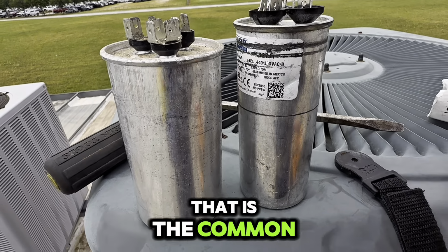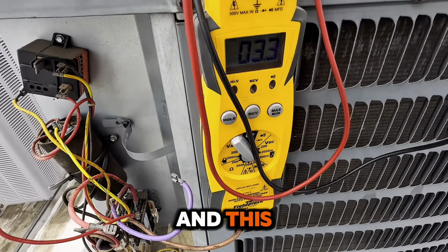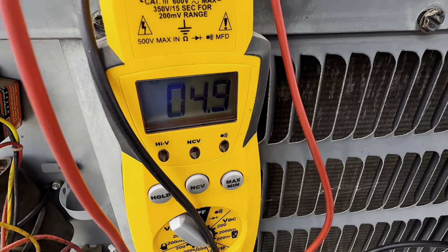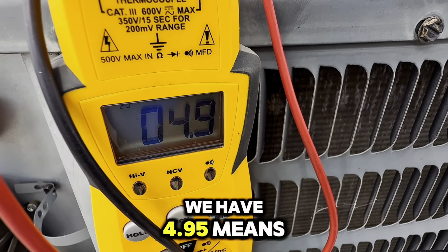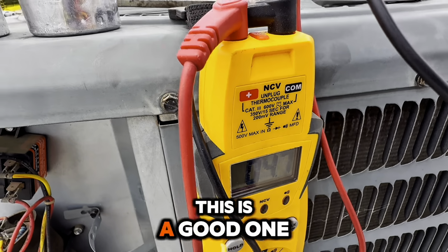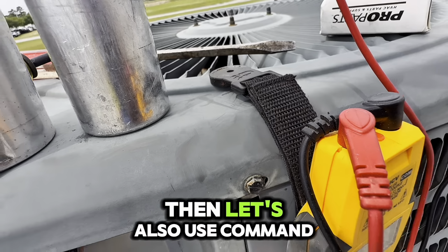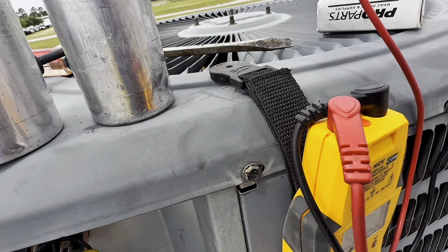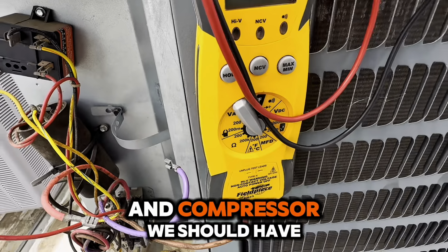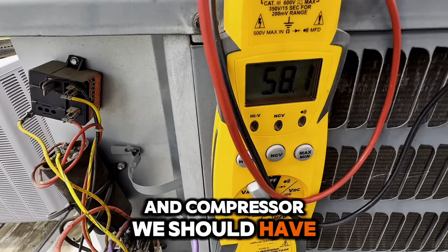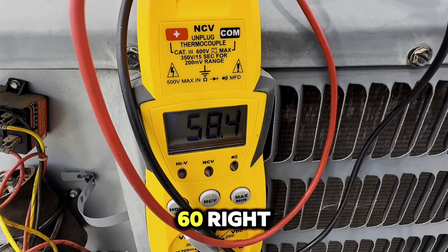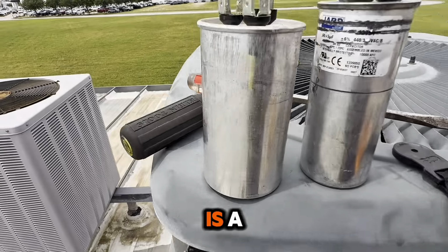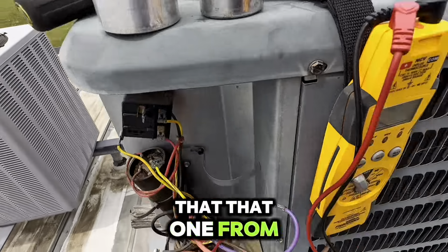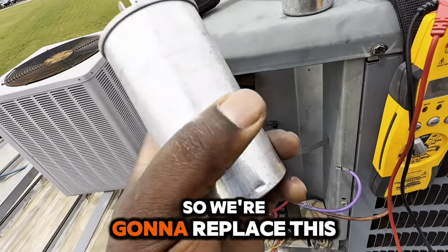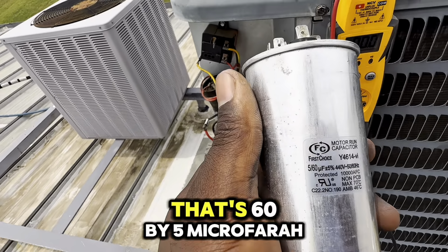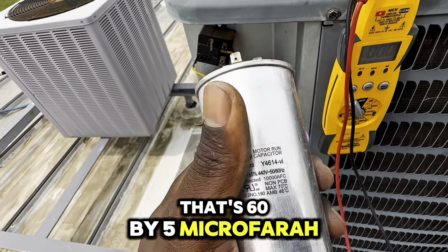So let's test this one that we assume is working. That is the common, and this, that is for the fan. We have 4.95, means this is a good one. Then let's also use common and compressor. We should have 60, right? Average 60. So the one from this unit is bad, so we're gonna replace this one. Okay, that's 60 by 5 microfarad.